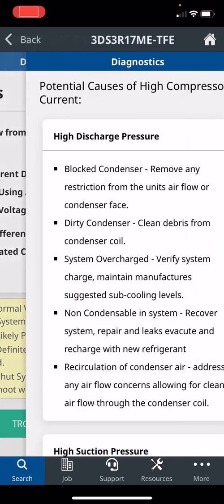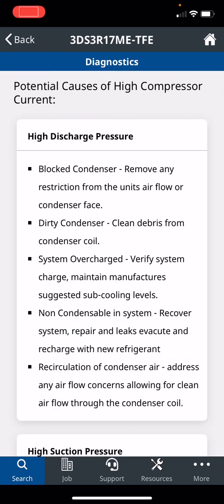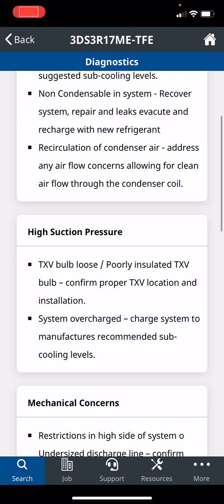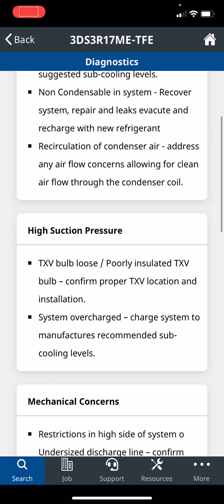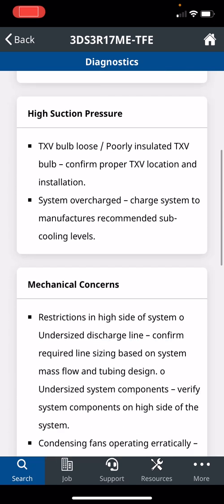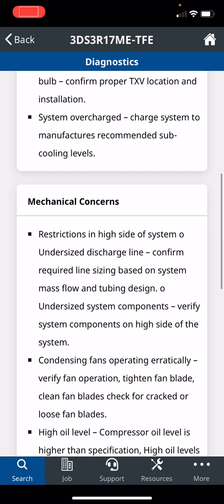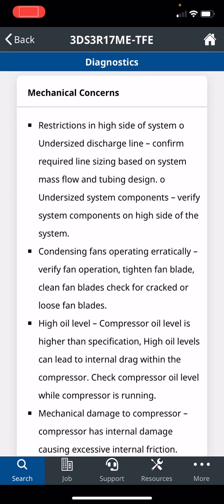If you're between 0 and 10%, normal variation, so that means that system is running as efficient and effectively as it should be. But if you get over 10%, there's likely a problem. If you click on troubleshoot, here is a guide to help you start looking at things. Take off the blindfold of chasing your tail. This is a place where it can give you a starting point. Check the condenser, is it blocked, is it a dirty condenser, is the system overcharged, is you got non-condensibles in your system, or are high suctions due to maybe the bulb or the system is overcharged, or mechanical concerns. It gives you steps to check.